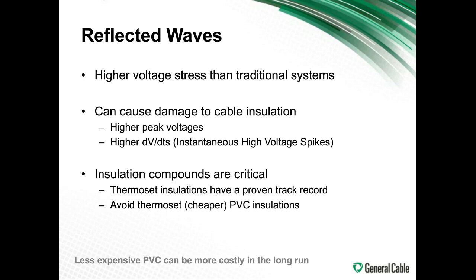This can cause damage to the cable insulation. These higher peak voltages definitely create problems in insulation, and you see instantaneous high voltage spikes, which we call high dV/dt. So it's a change in voltage over change in time. The insulation compound, the material that the cable is made of, becomes very critical. You want to make sure that it does not get damaged by this kind of phenomenon. So thermoset insulations have a proven track record for alleviating that. Thermoplastics, sorry, there's incorrect information here. PVC insulations actually cause issues. I'll go over that in a minute.